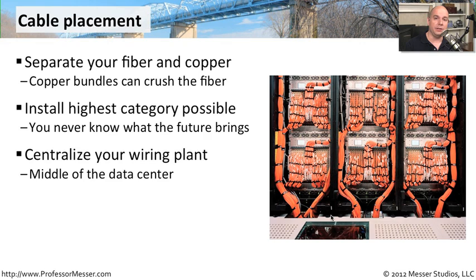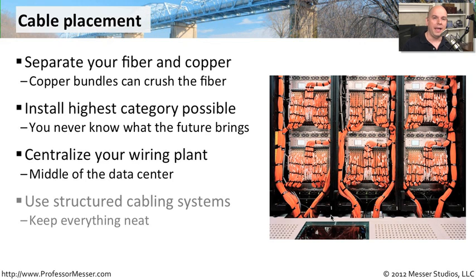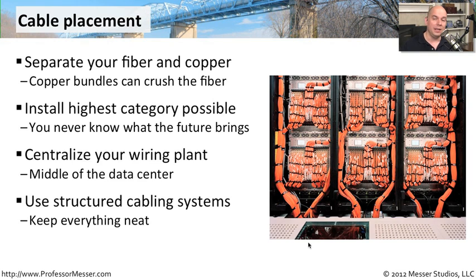Your wiring plant in your data center needs to be centralized so you can keep the runs of wire to a minimum, with everything in the middle of the data center, making it very easy to distribute cables wherever you need. If at all possible, use a structured cabling system that keeps all connections neat. Nothing should be crimped with cable ties — use Velcro to make sure none of the cables have been kinked, avoiding any shorts or opens, giving you the best possible cabling system. When it's set up like this, cables aren't really going to be your first problem.